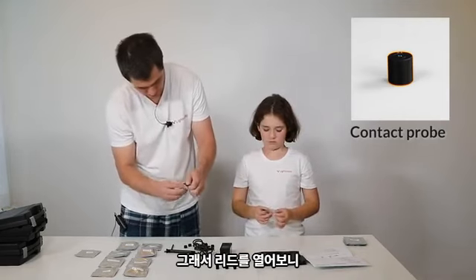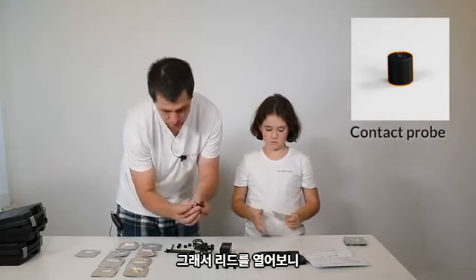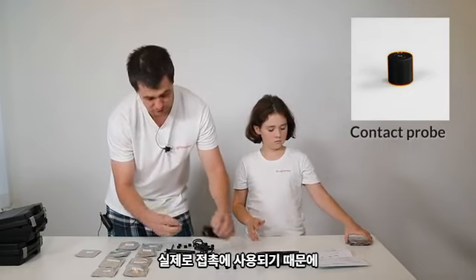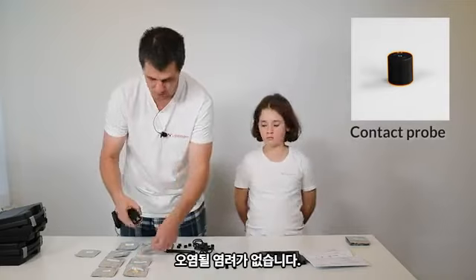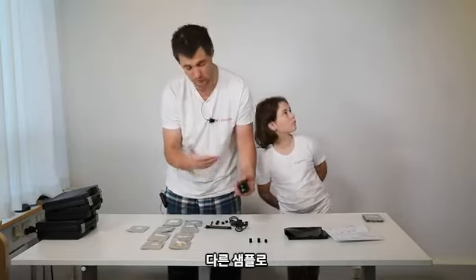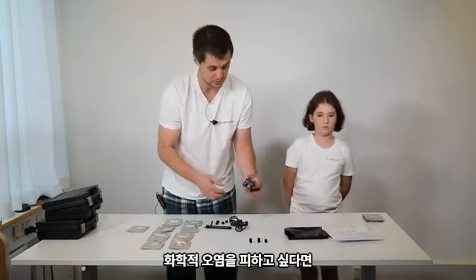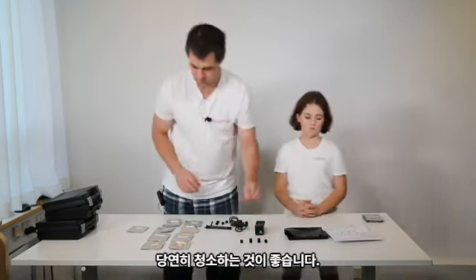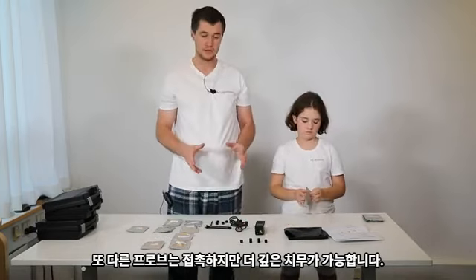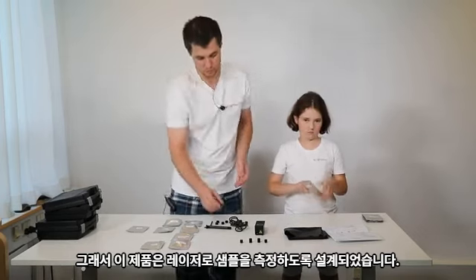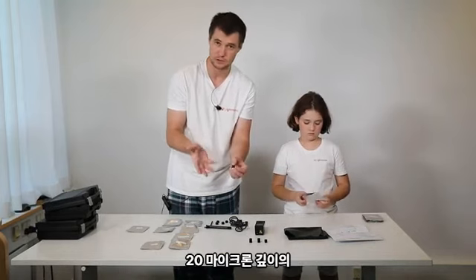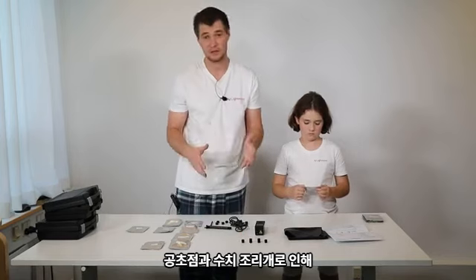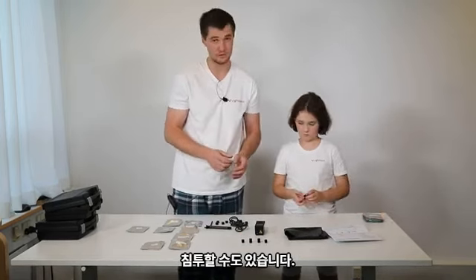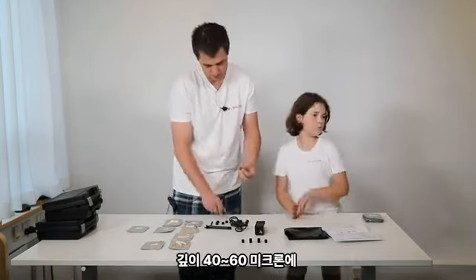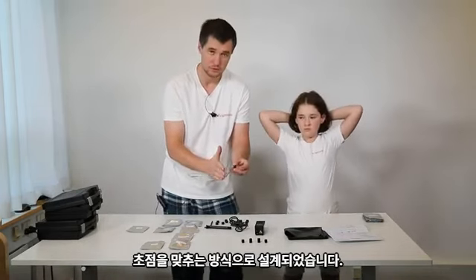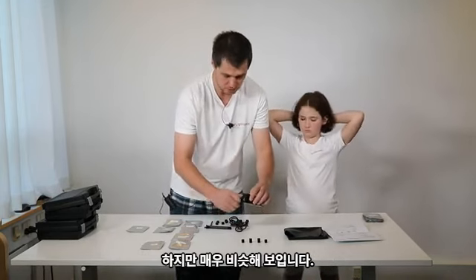Fantastic. So I open the lids and you can see contact probe allows you contact, and you should not worry on contamination touching it by finger because it's actually used for the contact. But of course we recommend to clean it if you want to avoid any chemical contamination from one sample to another sample. And it's ready to go. Another probe would be also contact, but with deeper penetration. So this one was designed to measure samples with laser spot approximately on a surface on a probe, but it will also penetrate because of confocality and numerical aperture up to 20 microns in depth. This probe designed in a way that it will actually not measure the contact material, but it will focus a little bit in depth, 40 to 60 microns, but it looks very similar.